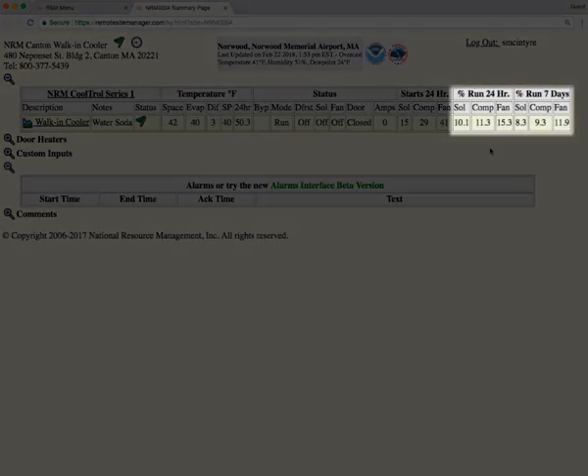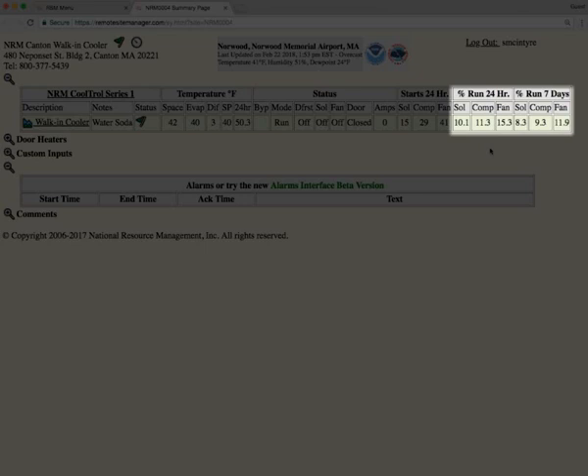Percent runtime, 24 hours, and percent runtime, seven days. This lets you know on how much the system is actually running in those time periods. So again, we have the solenoid column, which is the call for cooling, the compressor column, which is the compressor actually running, and the evaporator fan column, both for 24 hours and seven days.